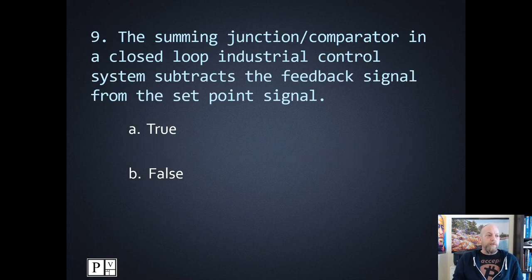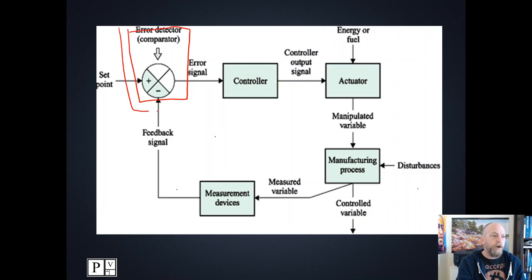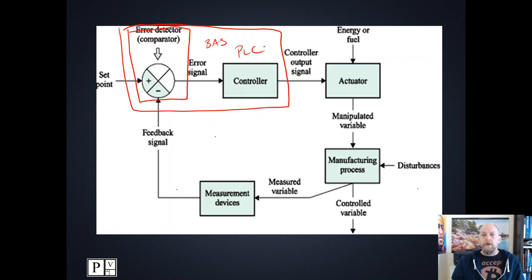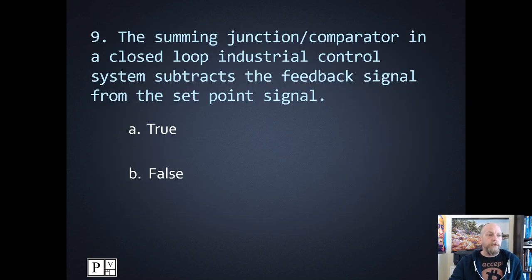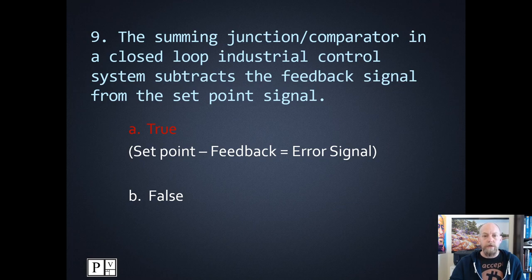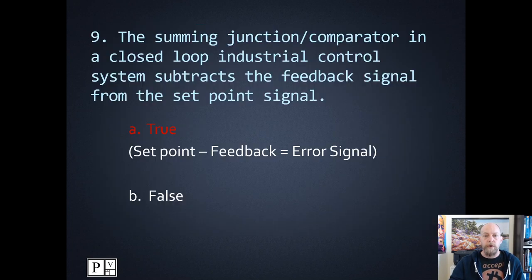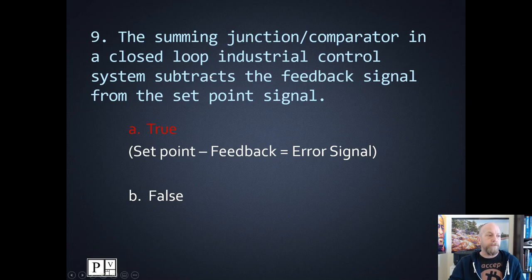Number nine: the summing junction or comparator in the closed loop industrial control system subtracts the feedback signal from the set point signal. The summing junction is right here in the block diagram. Keep in mind that the error detector or comparator is part of the controller — part of the building automation system or PLC. It's taking the difference between the set point and the feedback signal, so that one's true. The error signal is the difference between those guys, and the controller tries to accommodate for that error by sending a signal out to the actuator.